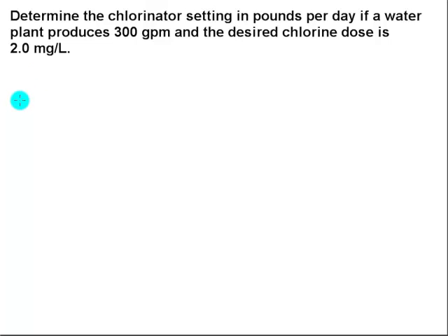Determine the chlorinator setting in pounds per day if a water plant produces 300 gallons per minute and the desired chlorine dose is 2 milligrams per liter. Well, I know from my pounds per day formula that the flow rate has to be in MGD, and they didn't give me the flow rate in MGD, they gave it to me in gallons per minute.